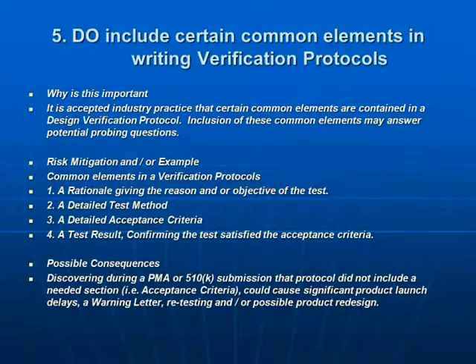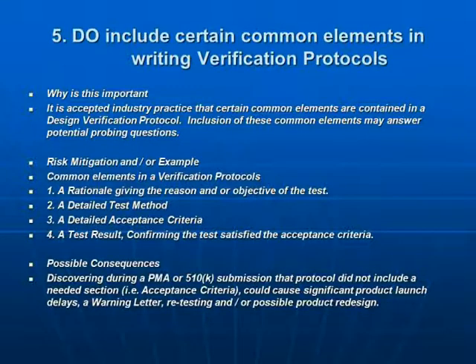The fifth do involves common elements in verification protocols. Although there are no official guidelines or directives on common elements needed in a protocol, it is accepted industry practice to include certain elements: a rationale or discussion of the test and its objectives, a detailed test method that is a step-by-step guide, a detailed acceptance criteria that is clear and concise, and a test result which clearly states the acceptance criteria has been met. These elements will help to avoid confusion when the final report is being reviewed.